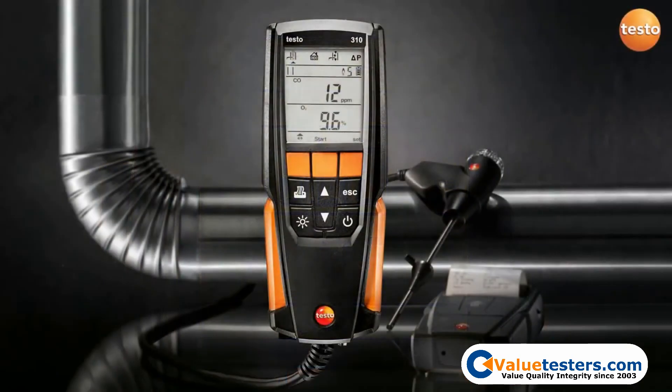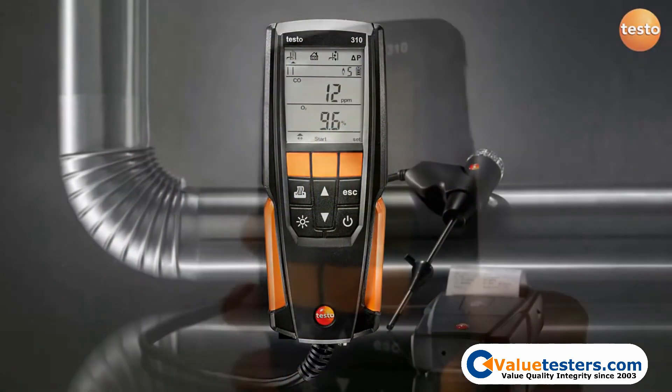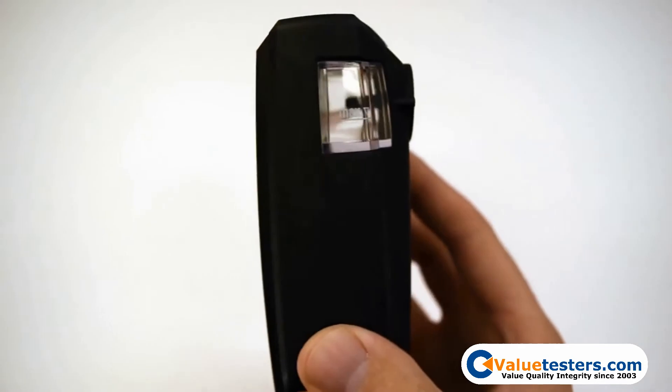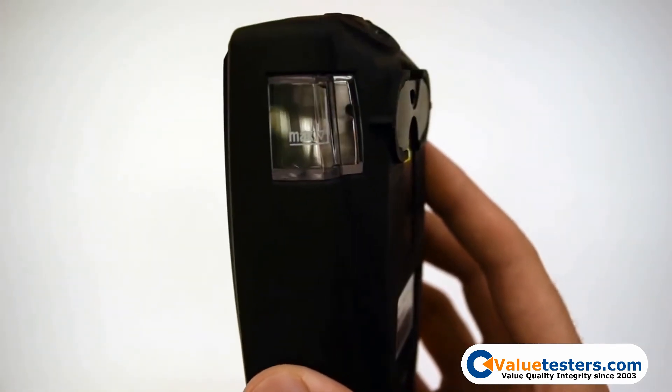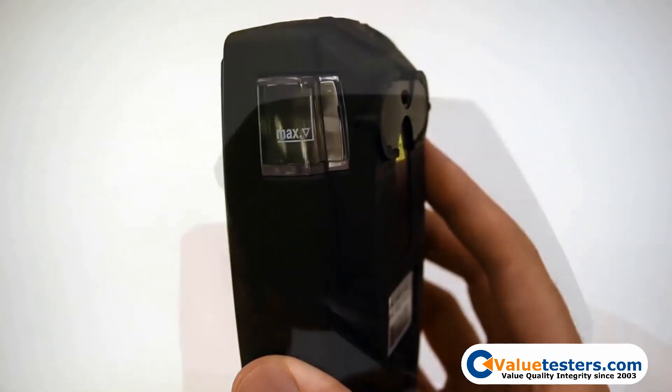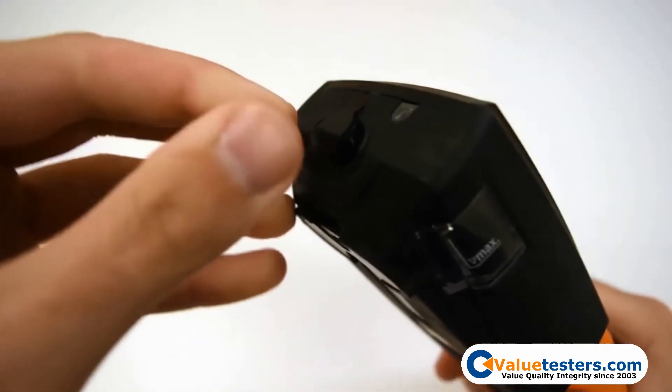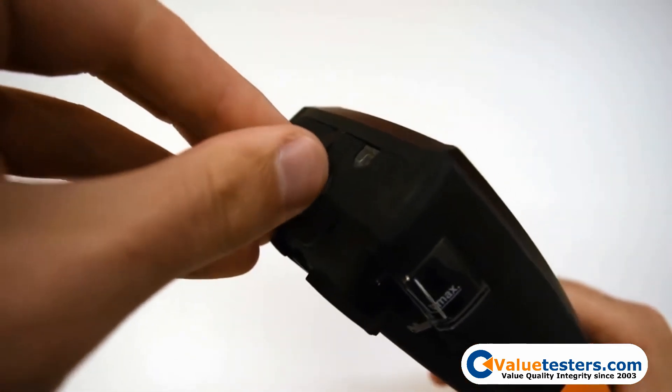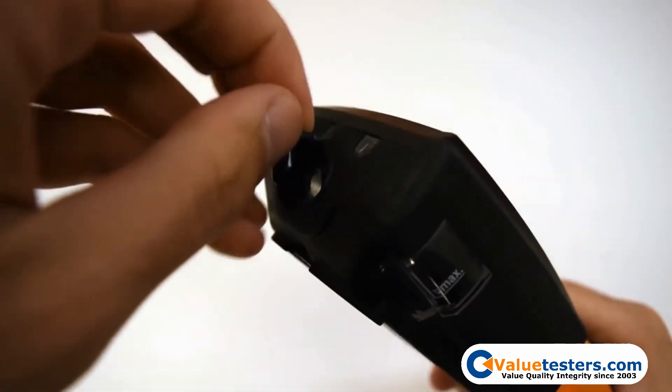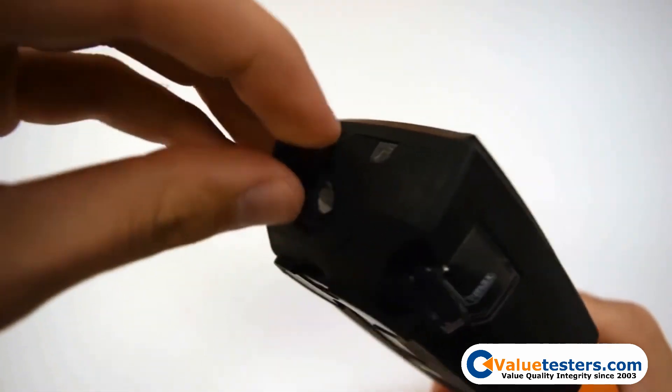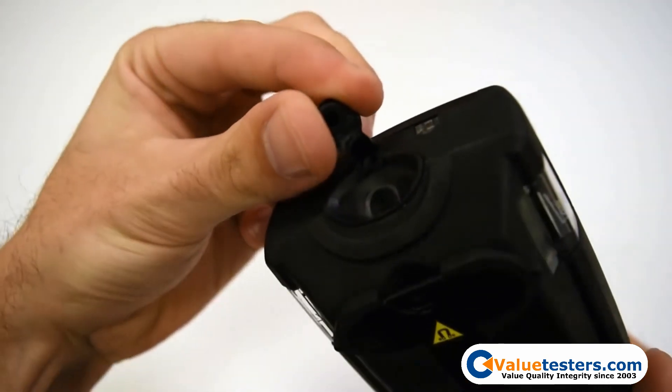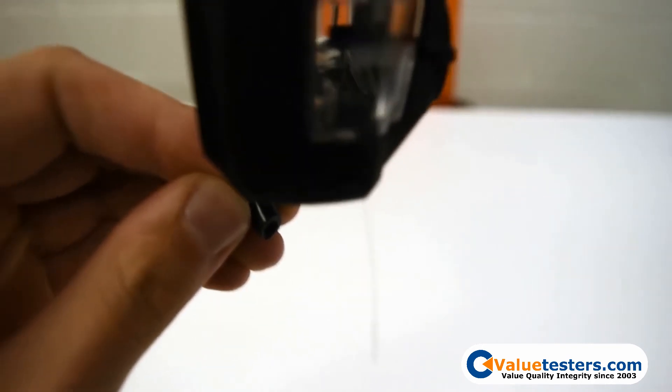A buildup in moisture will be collected in the condensate trap from continuous use. This level of moisture can be monitored by the view window located on the side of the instrument. The buildup in condensate can be emptied by pulling the condensate plug located on the top of the instrument and draining the liquid. Never let the moisture level reach the max fill line.